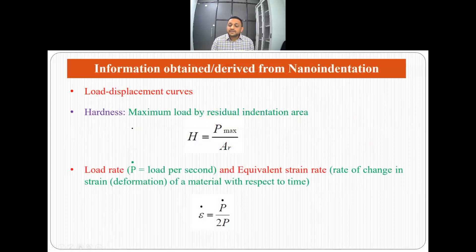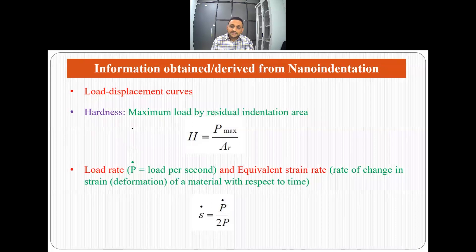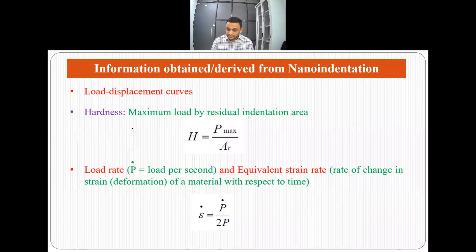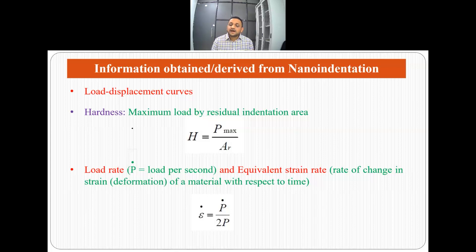What information can we derive or obtain from nano-indentation? The first information we directly obtain when performing a nano-indentation experiment is the load-displacement curve — that is, with increasing load, how far the tip penetrates into the sample. The second is hardness, which is the maximum load divided by the residual indentation area. When we divide the maximum load specified by us by the overall residual indentation area, we get the hardness of the material.